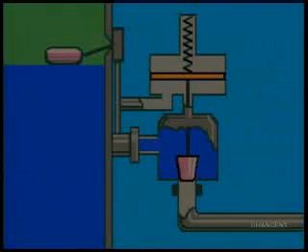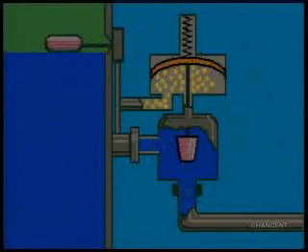Level control on the stripper is important in stabilizing operation. The level controller should be adjusted, as in the contactor, to hold a uniform flow rate of lean amine out of the stripper. Flow rate surges will cause the reboiler to operate inefficiently and may overload it.